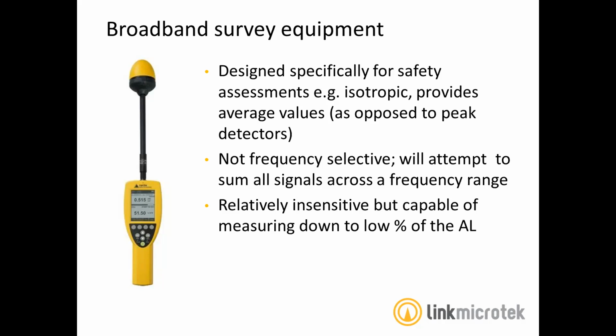The good thing about this type of probe is that the equipment is designed to see EMF as the human body does, so they're isotropic and average power detectors, because those action levels are largely based on heating effect to the body. The probes sometimes look a bit odd, and we've had people say to us, "Why is it on such a long stick?" And that's specifically to minimise reflections from the operator, so that it doesn't affect the measurements. It keeps the measuring end further away from the user.